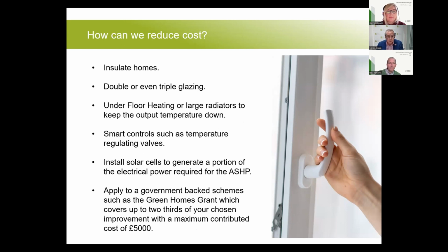Example 2 we had here, an existing house, which we did all the maths on. The existing gas boilers were running at 80 degrees temperature with a return of 60. Hot water was stored at 65 degrees, which we also had to do, otherwise you wouldn't have enough hot water. So to avoid adding any more radiators or replacing the existing ones with larger ones, to make up for those lower temperatures, we had a high temperature air source heat pump installed, which was actually Daikin Altherma 3, if you're familiar with that product. And that brought the SCOP down to about 3.58.